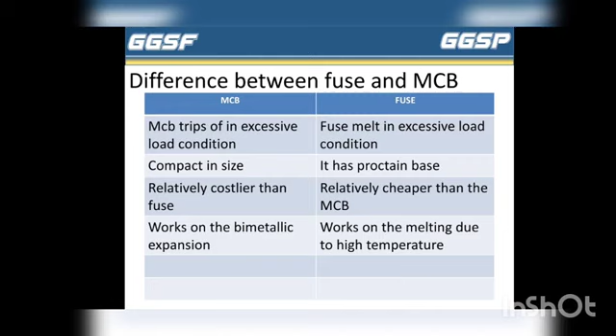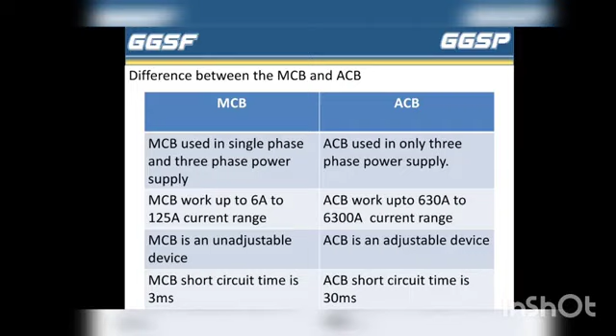Next one is difference between MCB and ACB. MCB is used for single phase and three phase power supply, and ACB uses only three phase power supply, meaning high current. MCB works up to 6A to 125A current range, and ACB works up to 630 ampere to 6300 ampere current range. MCB is an unadjustable device and ACB is an adjustable device. MCB short circuit time is 3 ms and ACB short circuit time is 30 ms.